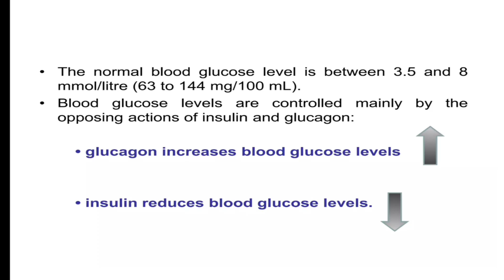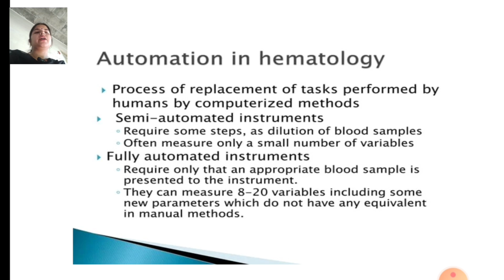In today's class, I discuss automation in hematology, the process of replacement of tasks performed by humans by computerized methods. Semi-automated instruments require some steps, such as dilution of blood samples, and often measure only a small number of variables. Fully automated instruments require only that an appropriate blood sample is presented to the instrument. They can measure 8 to 20 variables, including some new parameters which do not have any equivalent in manual methods.